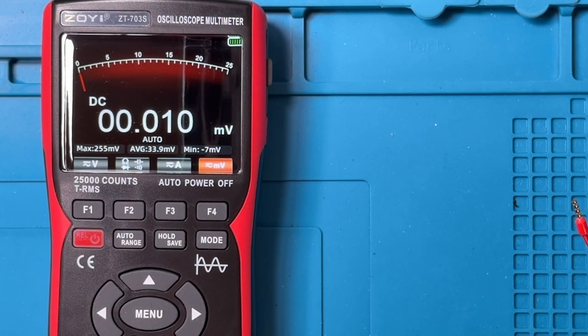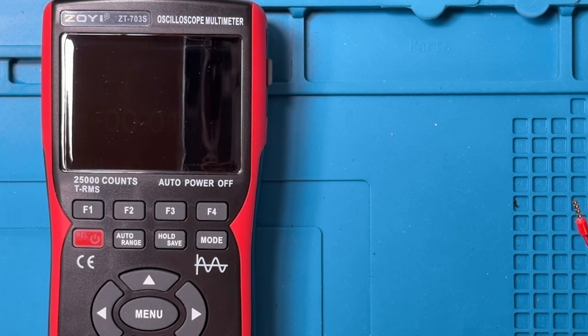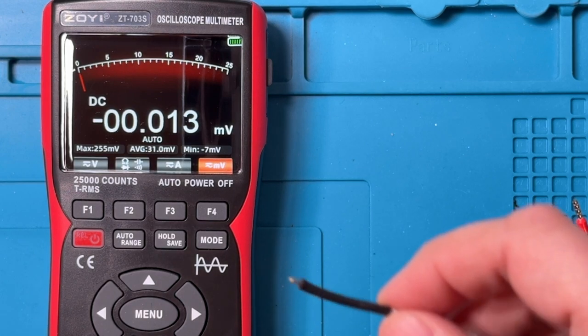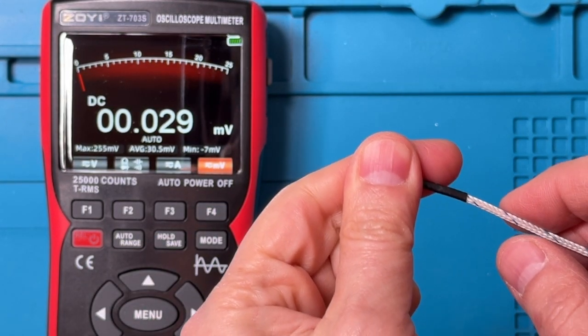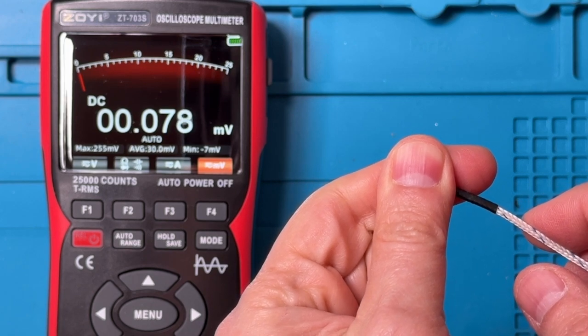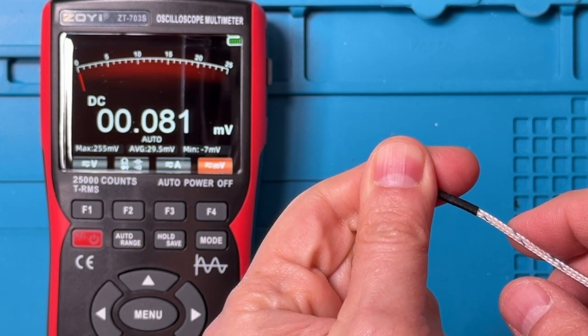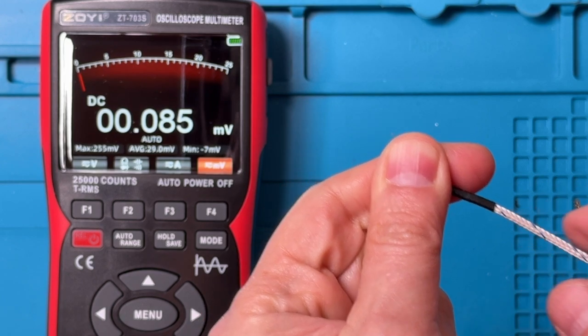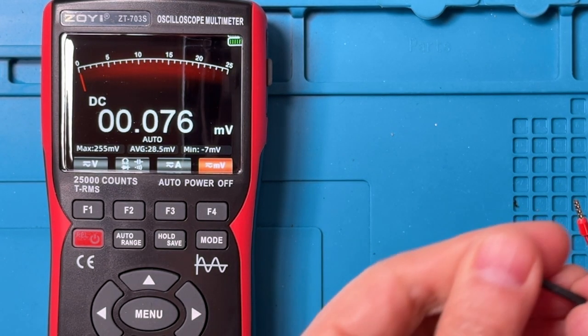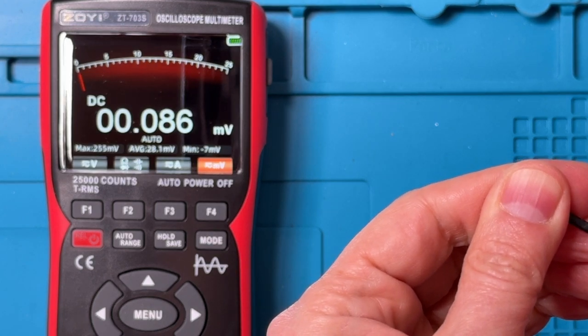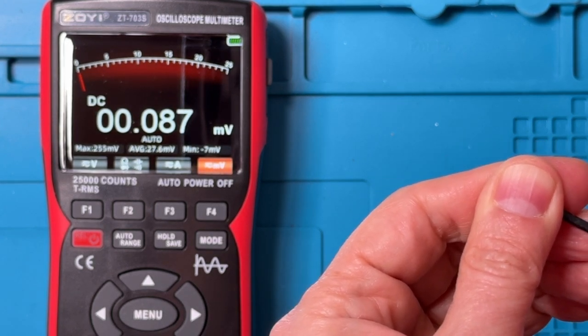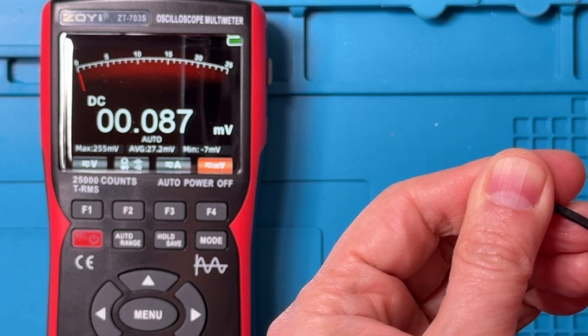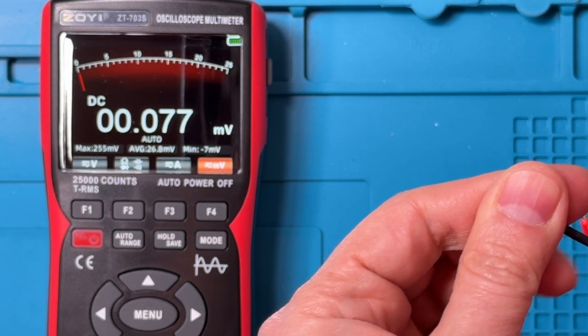I don't have a reference source for DC millivolts, but I have found that my fingertips will generally be able to warm up a temperature thermocouple so that it gets to about 0.06 millivolts. So let's try that out. I've plugged in the thermocouple here, and my fingers, if they're warm enough, there we go, 0.06, 0.07, 0.08. So it seems to have good resolution there, although, like I say, I can't really tell you whether or not that's an accurate millivolt reading because I don't have a reference source there.